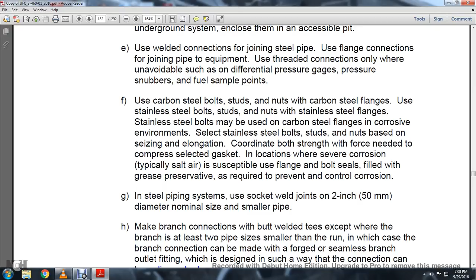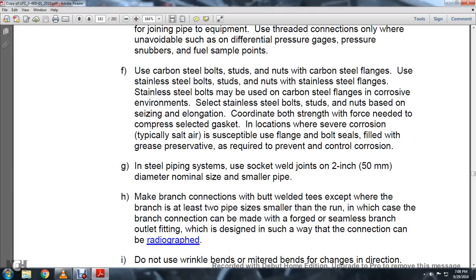In steel piping systems, use socket welded joints on pipe of 2-inch nominal diameter or smaller. Make branch connections with butt weld tees, except where the branch is at least 2 pipe sizes smaller than the run. In that case, the branch connection can be made with a forged or seamless branch outlet fitting, which is designed in such a way that the connection can be radiographed. Do not use wrinkle bends or mitered bends for changes of direction.